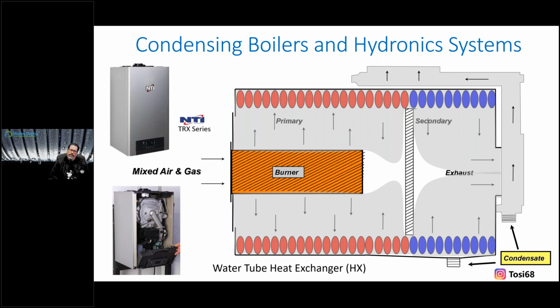It's energy in, energy out, or what flows into a T flows out of a T. So we're transferring through the process of maybe our primary, secondary piping, and all the boiler is doing is trying to exhaust all this heat energy into that volume of water, which is usually a low volume. So the key there is that the circulator is always dedicated to that heat exchanger, so we don't ramp up, we don't overheat and go off on a high limit.